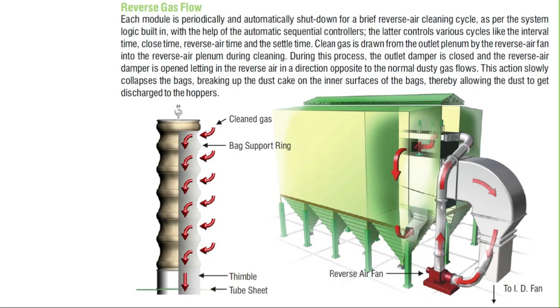Reverse Gas Flow: Each module is periodically and automatically shut down for a brief reverse air cleaning cycle as per the system logic. With the help of automatic sequential controllers, various cycles are controlled — including interval time, close time, reverse air time, and settle time. Clean gas is drawn from the outlet plenum by the reverse air fan into the reverse air plenum during cleaning. During this process, the outlet damper is closed and the reverse air damper is opened, letting in reverse air in a direction opposite to the normal dust gas flow.